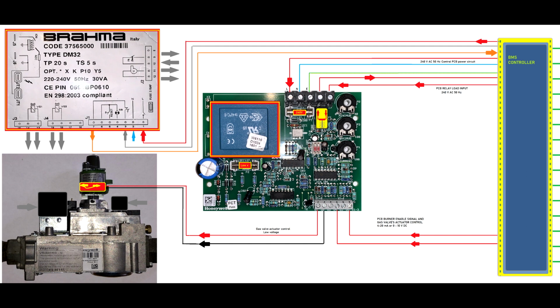When the Brahma controller is first powered up, you will send the signal to this building management control. You see one of these wires, I think it is number 7, is orange and goes into this building management control, but the signal is not returned yet. When the heat is on demand, the building management control will close the circuit, and you'll see just now the other cable become orange, which means the circuit is closed. Now the circuit is closed and the Brahma controller will start to initiate the heating protocol.